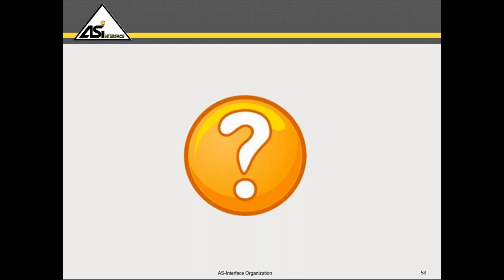Okay, so most everything the 2 gentlemen talked about was on a conceptual level, assuming that the AS interface safety, I don't want to say safety chip, but the safety portion was integrated into the device. If you want to use a conventional safety e-stop, let's say, that has dry contacts, what you would do is you would purchase from any of the many manufacturers a safety coupling module. It looks like a standard AS-i module, but has the safety circuit in there so that it has a safe input. And then the 2 dry contacts from your safety device are simply connected to those inputs, and that together serves exactly the same purpose.